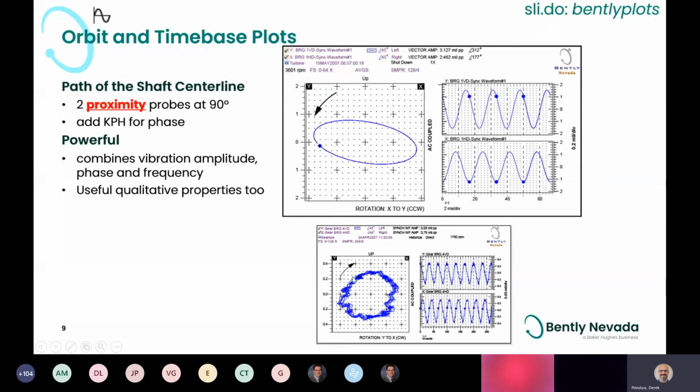There's noise along here. And generally speaking, this sort of chaotic noise is going to be a result of the shaft surface condition. The messier or the more scratched up your shaft surface is, the messier your direct orbit is going to be. Even in the extreme event that there's a sharp scratch in the target surface, you might see things like a little ear poking out here in the direction of each of the X and Y probes.